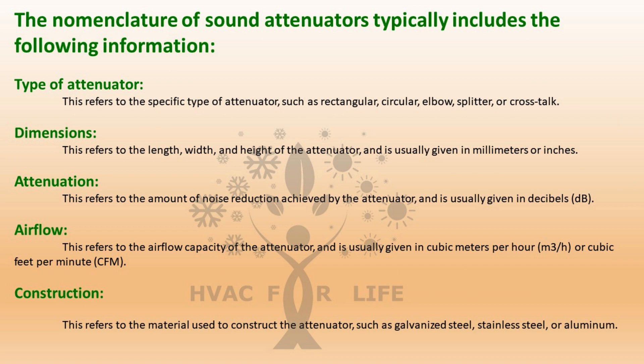Type of attenuator: this refers to the specific type such as rectangular, circular, elbow, splitter, or cross-talk. Dimensions: this refers to the length, width, and height of the attenuator, usually given in millimeters or inches. Attenuation: this refers to the amount of noise reduction achieved by the attenuator, usually given in decibels (dB). Airflow: this refers to the airflow capacity of the attenuator, usually given in cubic meters per hour (M3H) or cubic feet per minute (CFM).